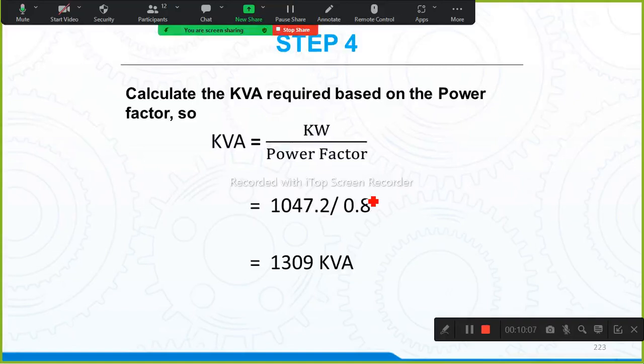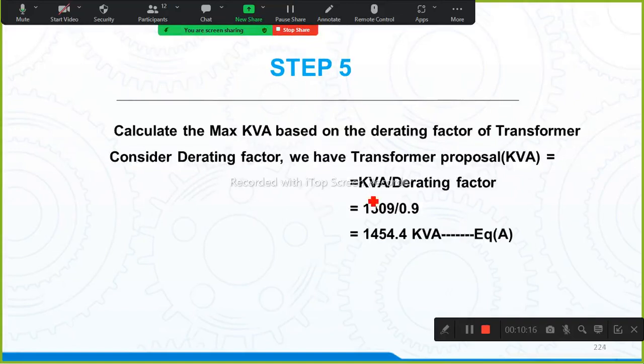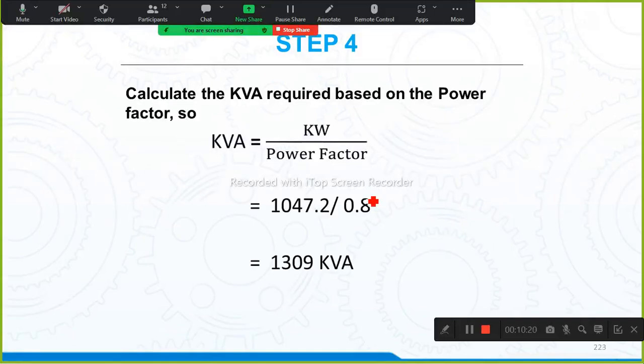जो भी transformer है will not going to give any 100% efficiency. So considering the derating factor of the transformer. So what is the derating factor of the transformer? We know that the derating factor of the transformer is the efficiency of the transformer, which is 90%. So calculate, because अभी मैं ये 1309 KVA लगाया तो मुझे exactly 1309 KVA चाहिए, बट मुझे पता है कि every equipment will not give any 100% efficiency. So considering the losses which have been produced by the transformer, we need to calculate what is the maximum KVA that can meet your total demand.